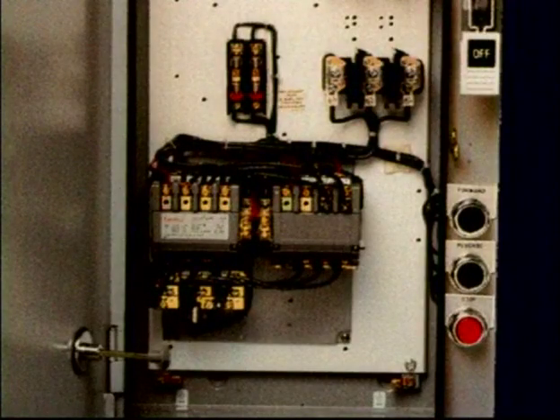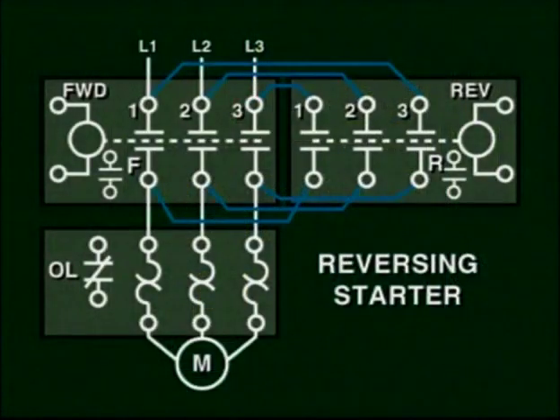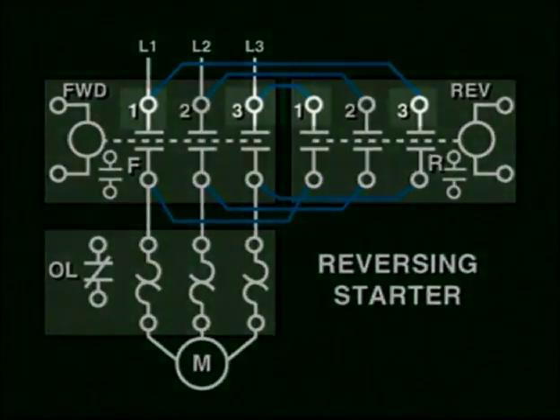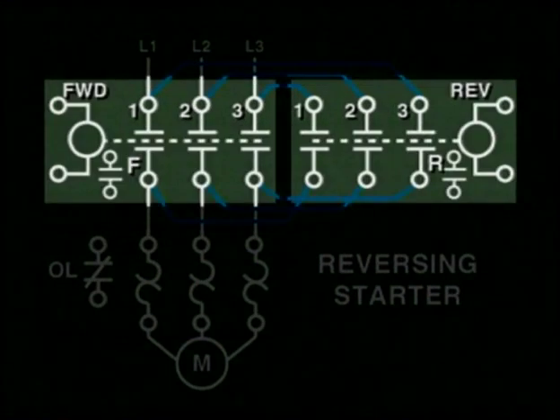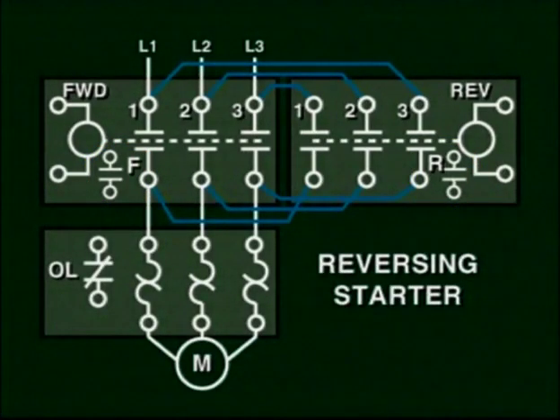Reversing starters are available for applications which require reversal of motor rotation, that is, forward and reverse. These reversing starters can be used with plugging switches in a circuit, as we'll see in a little while, to reverse the direction of the motor. We know that a three-phase motor can be reversed by simply changing any two of the three phases. The reversing starter provides the hardware to implement this reversal. This starter is composed of two contactor sections with their respective auxiliary contacts. These sections are used to switch the phases to the motor. The starter also provides the overload protection for the motor.